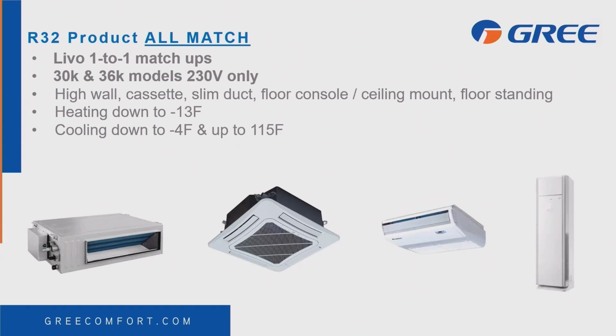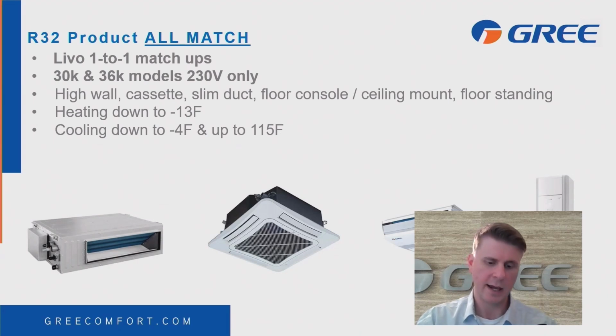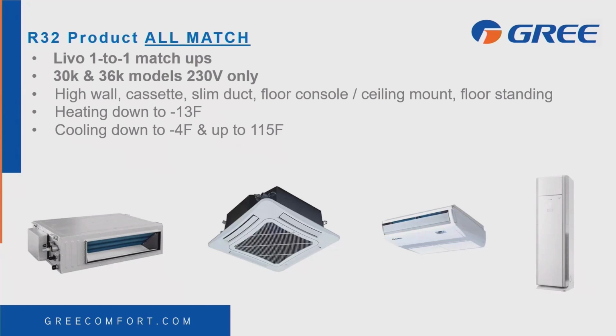So now we'll move on to the 30 and 36K models. So with the slim duct, cassette, floor ceiling, new floor standing model, these will be available in 30 and 36K models in 230 volt only. However, due to the size being 30 and 36K, these are only compatible with the Livo in 30 and 36K. So what we're seeing is 9 through 24 is not compatible with the Livo, only on the 30 and 36K. And so because of the outdoor unit capacity, you're only going to get the heating on these down to -13, cooling down to -4 and up to 115.